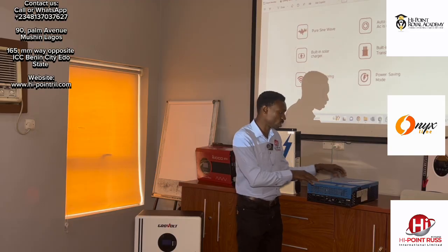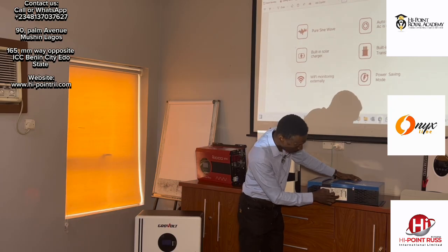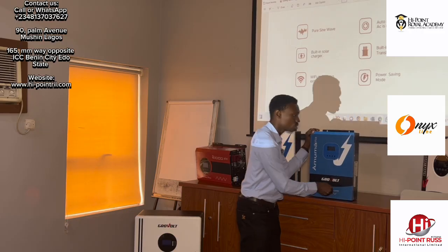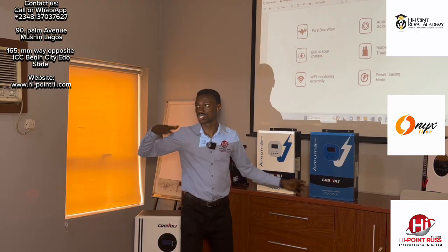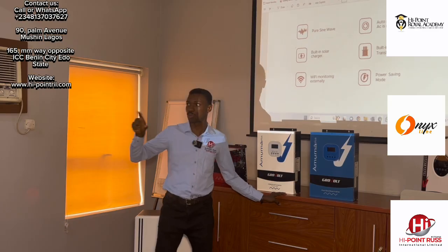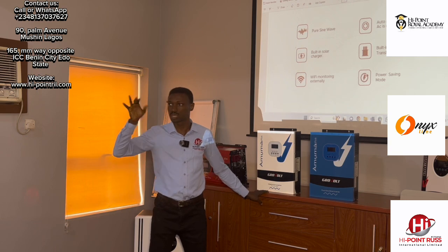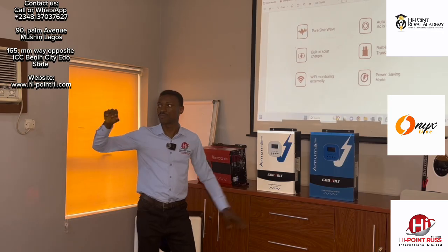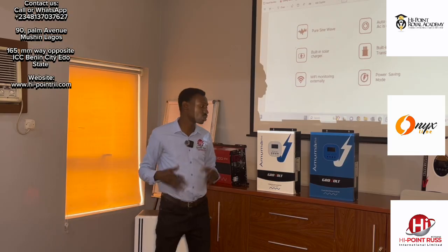Good. It has that, but in this case, if we open up the screws inside, for this particular model, this is a 3 kVA model, it has it inside. So input protection is very important so that the device will not just suffer AC fluctuation in the AC voltage in your grid and all that. But that does not stop us from always using our appropriate protection devices, your SPD, your breakers. Yes, always still use that. So that gives us two levels or two steps of protection. If the electricity did not cross this one, this other one can shock it, something like that.